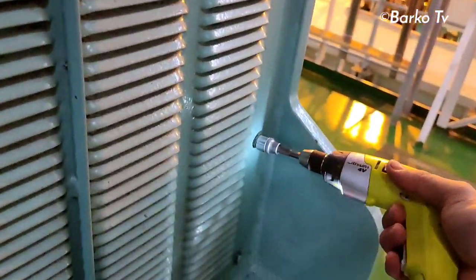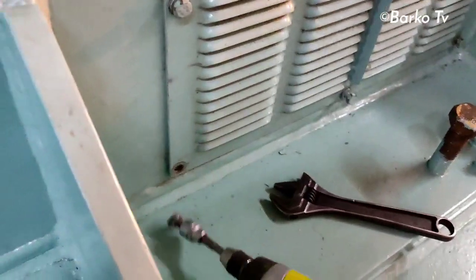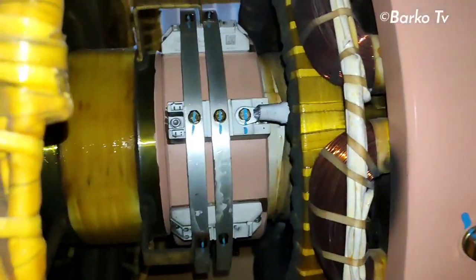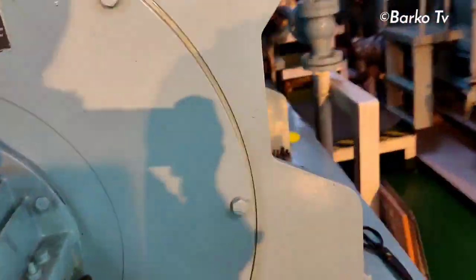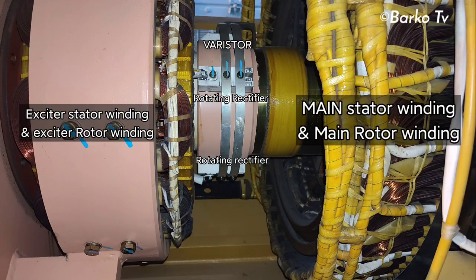We need to open this cover for the alternator where we can see the exciter rotor and access it properly. After removing the filter cover, the parts you can see are: varistor, rotating diode, varistor, varistor. On the right side: exciter stator and rotor. On the left side: main winding stator and main winding rotor, as well as the exciter stator and exciter rotor.